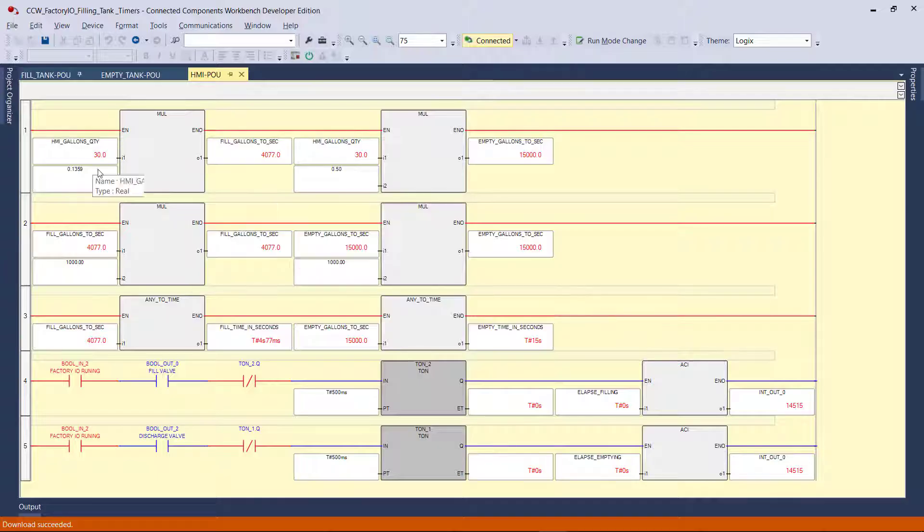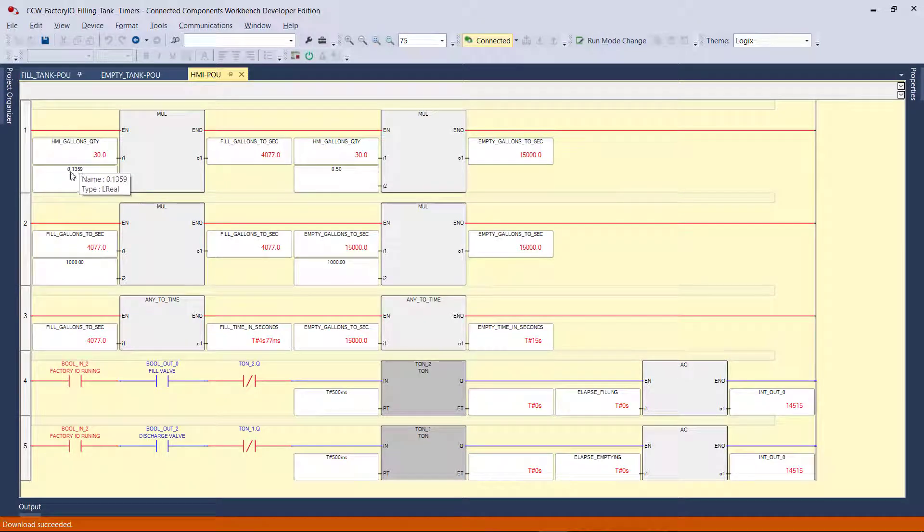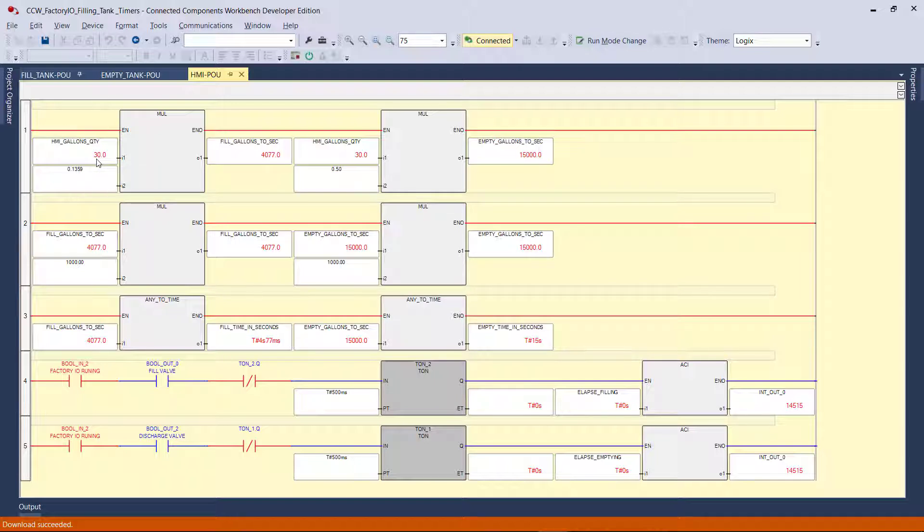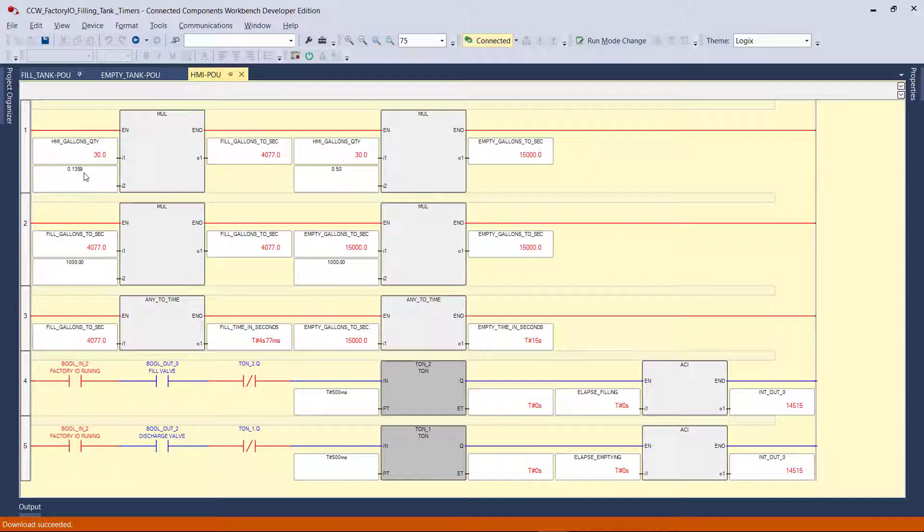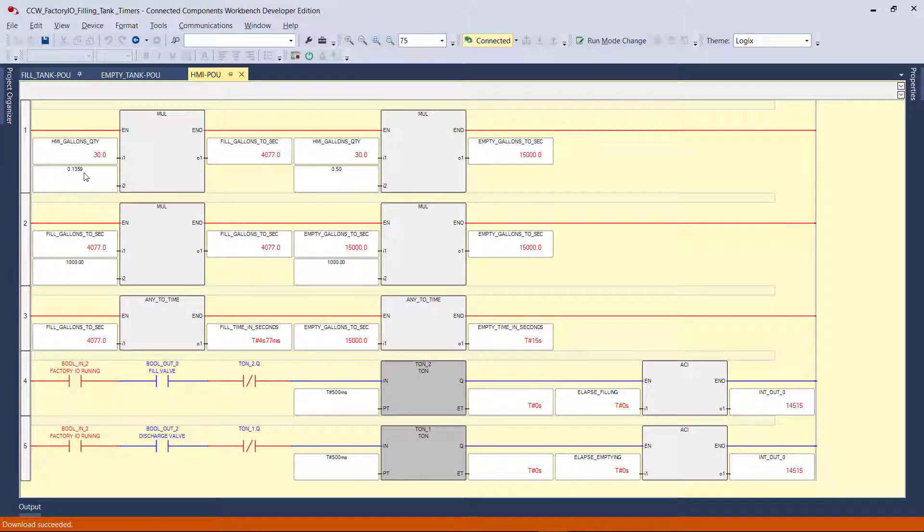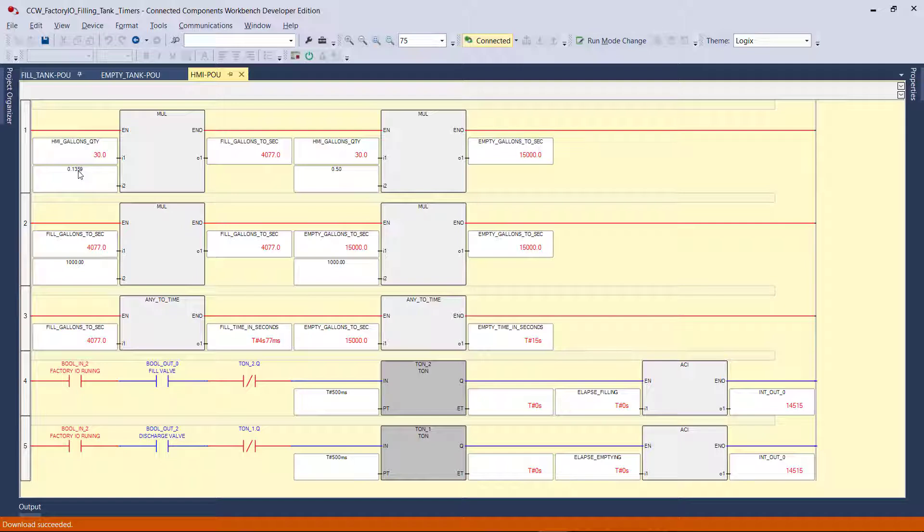So over here, we've got this variable called HMI gallons, that's how much gallon we need to fill the tank with. Over here, this is just a variable, a number that I figured based on testing. I turned on the valve, that was the fill valve, and I turned it on for five seconds just to test and see how many gallons it would give me. It gave me close to a certain amount. So I divided by the number of seconds, and this is the variable, the set point that I got per gallon. So it's 0.1350.